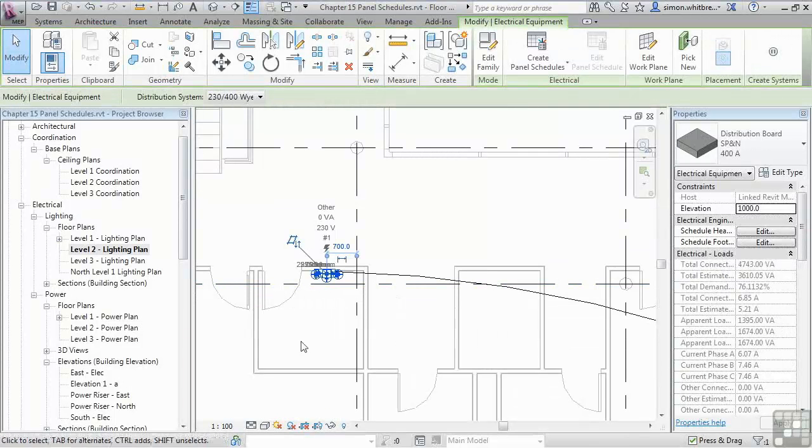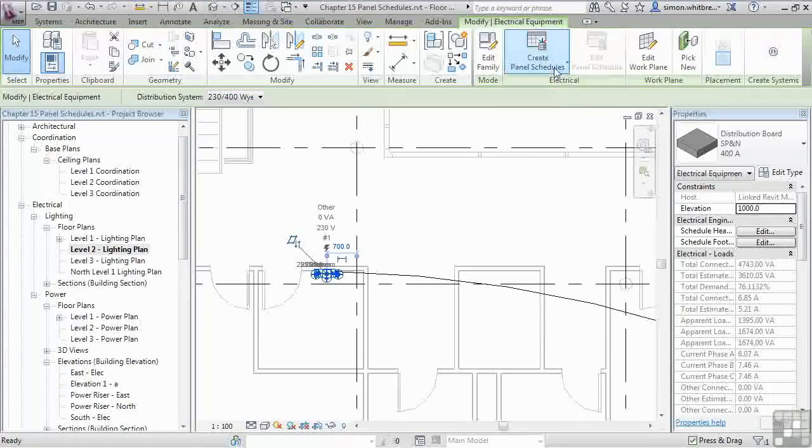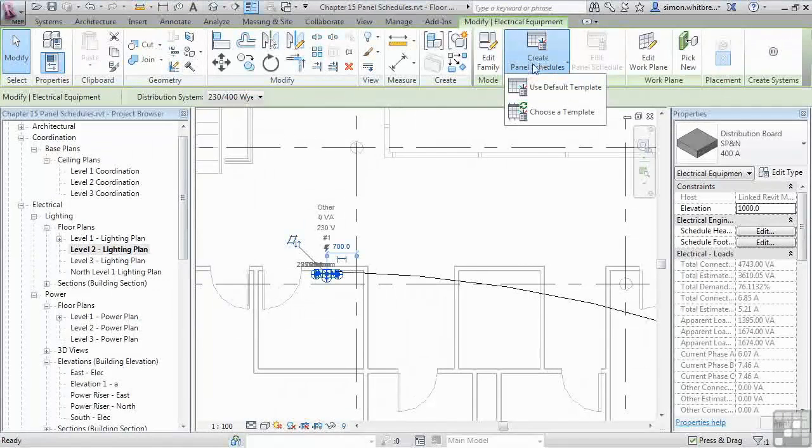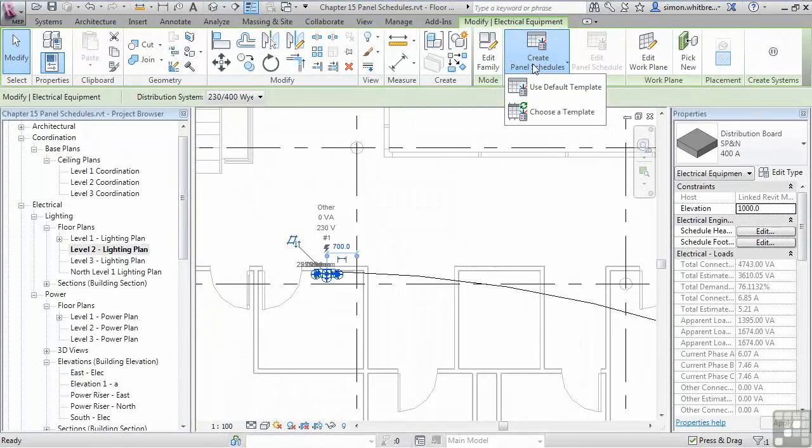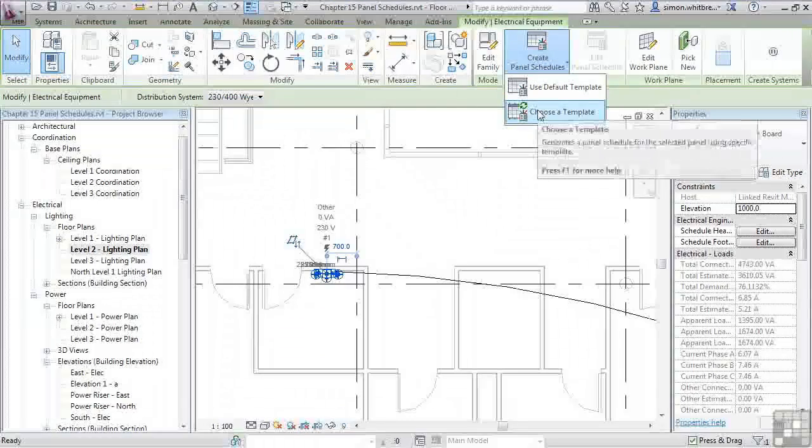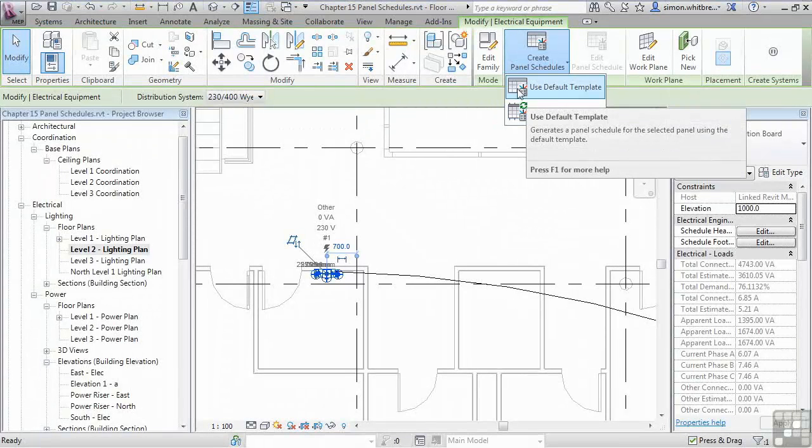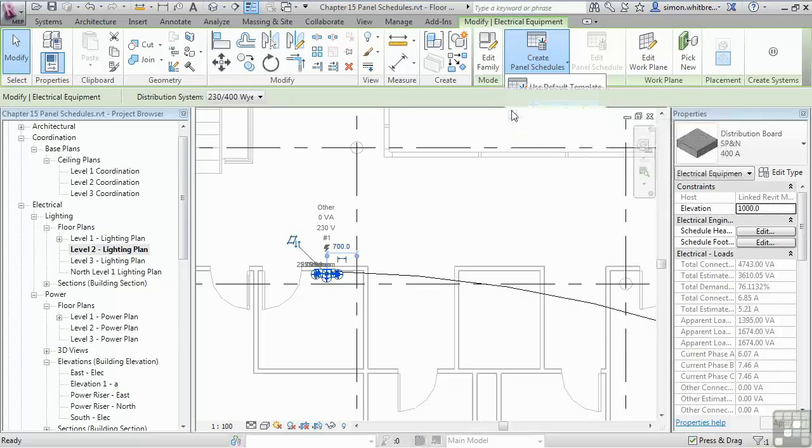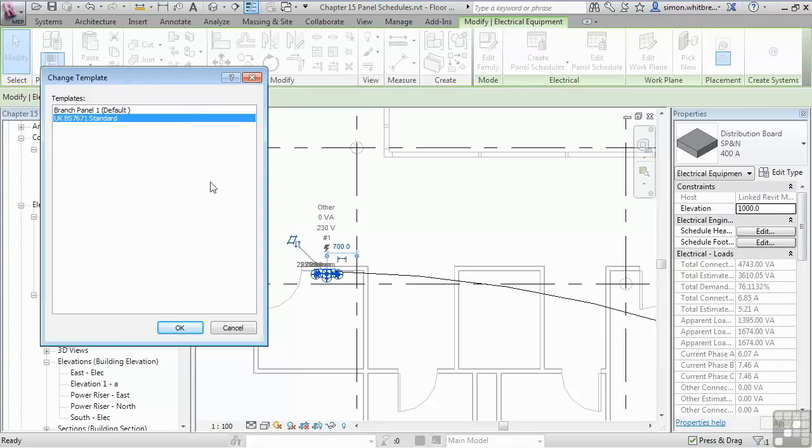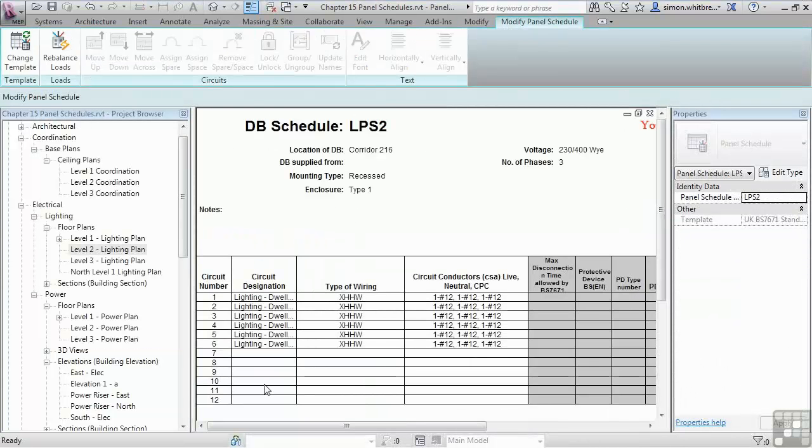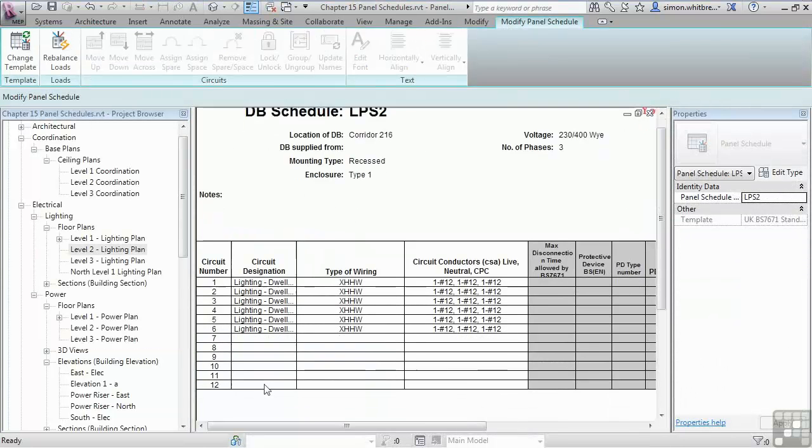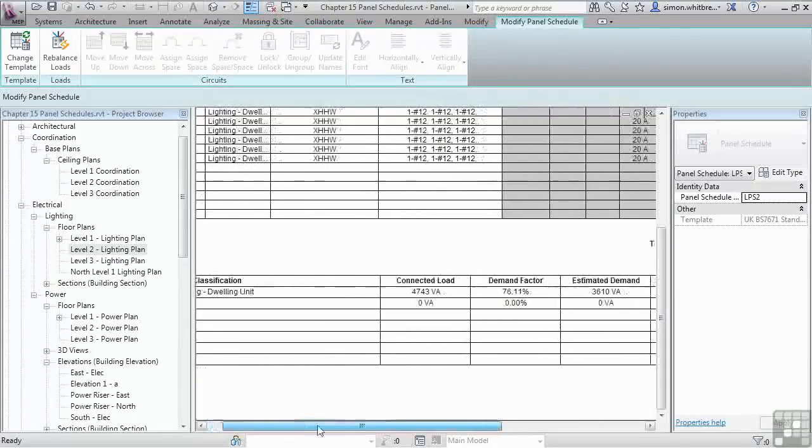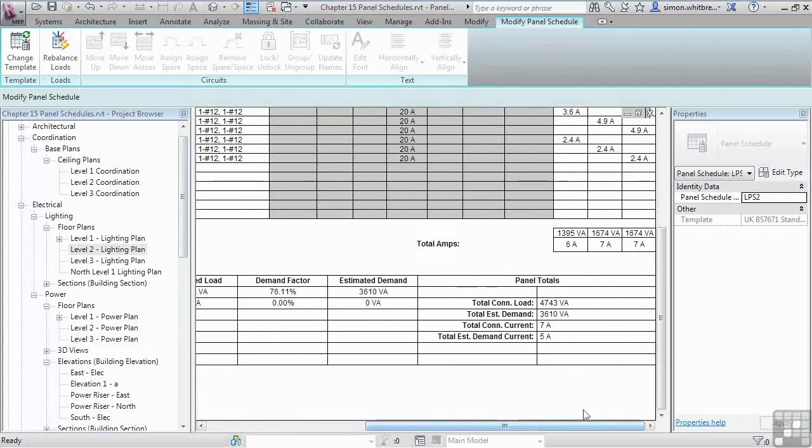If I select the panel itself, from the contextual tab on the ribbon we can create a panel schedule. We can choose a template or use a default template. Let's choose a template. We've got a predefined template here to a British standard. Click on OK. This gives us a panel schedule with all the loads associated with the circuits.